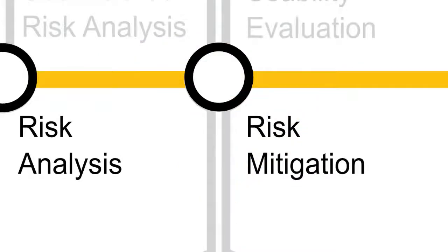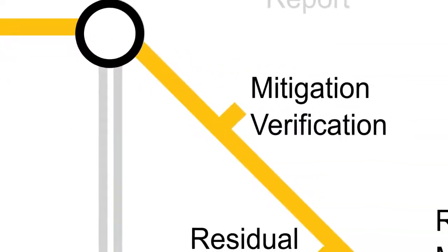These mitigations must be tested to see if they work and whether they introduce new risks or use errors into the device design. The results should feed back into design controls and human factors evaluation. Once it looks like the mitigations are effective, you'll want to generate test data that verifies they work. This is usually done as part of design verification and design validation steps on other tracks.